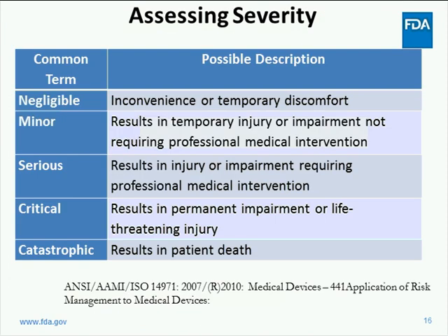With respect to assessing severity of patient harm on the x-axis, manufacturers should already have processes and experience for assessing the severity of impact of device defects on patients. Shown here is a suggested approach from ISO 14971. Generally speaking, the severity of patient harm increases from minor and temporary and inconsequential up to requiring medical intervention and death. While this is a suggested approach, the intent of the guidance is to align with current manufacturer processes, and the terminology used could be from already established risk assessment methodology.